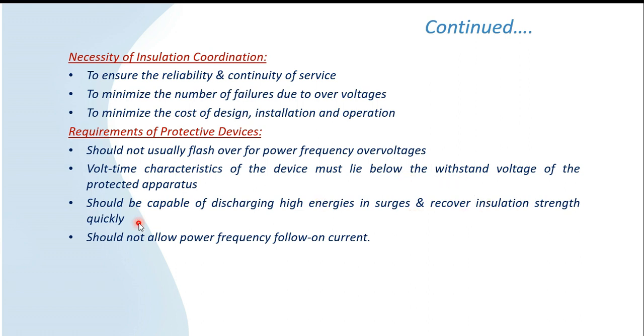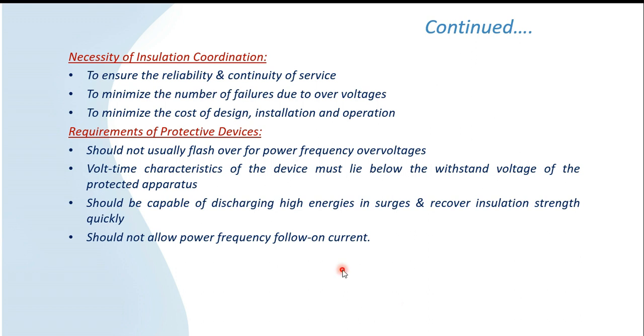The protective device should be capable of discharging high energies in surges and recovering insulation strength quickly. Once flashover occurs in protective devices after the surges, it should recover quickly and should not allow power frequency follow-on current. Power frequency follow-on currents are short-circuit currents flowing through the protective devices after the fault is over due to the existence of an arc. The arc or surges should extinguish quickly.